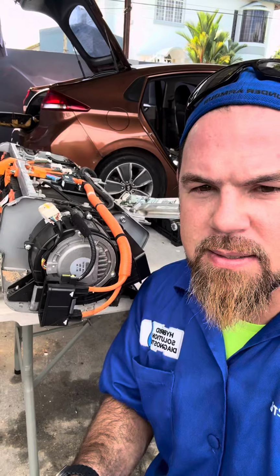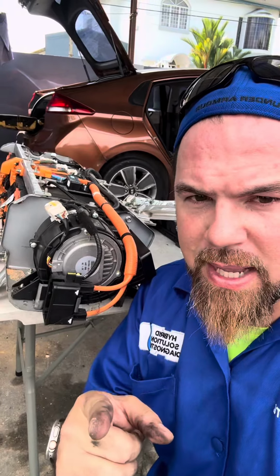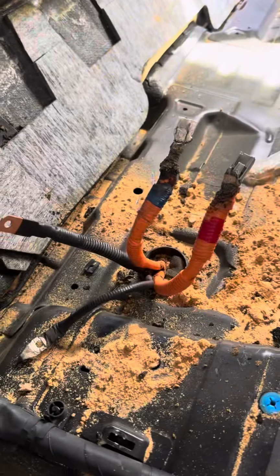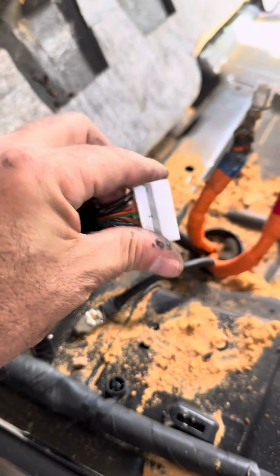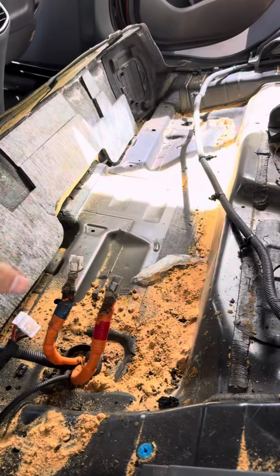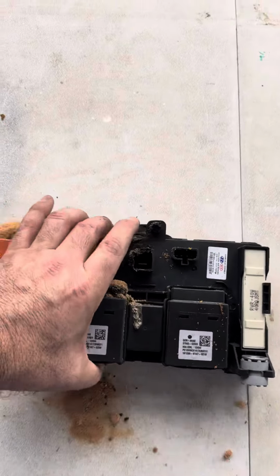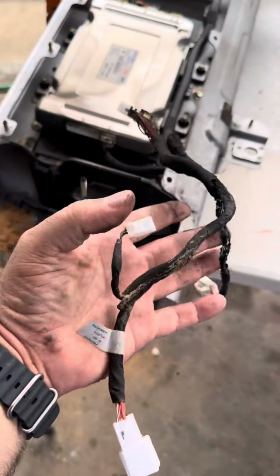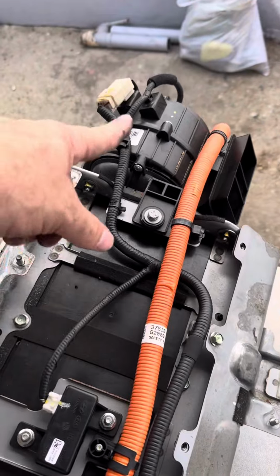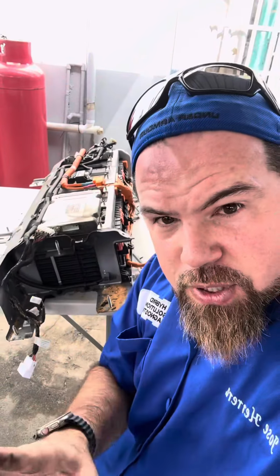Applying preventive maintenance to the high voltage battery could prevent catastrophe from happening. And the good thing is that the communication cable is completely fine. So just a cleaning, replacing these two cables, replacing a new junction box, and replacing the communication cables of this battery that connect to all the sensors, including the fan, should solve this issue with absolutely no problem.